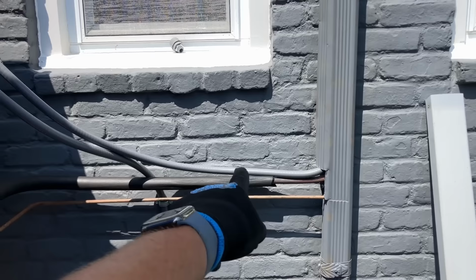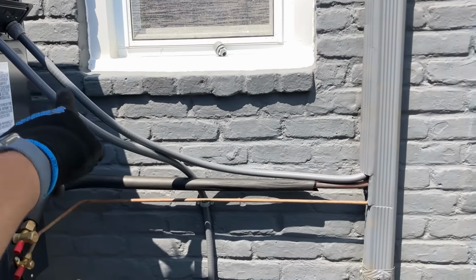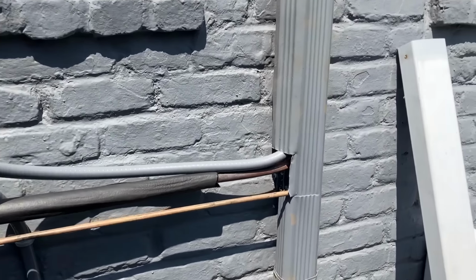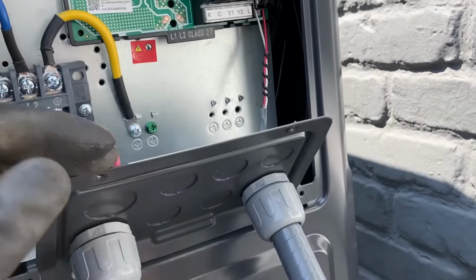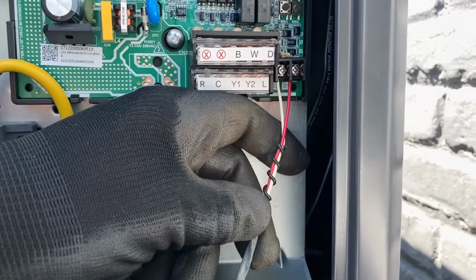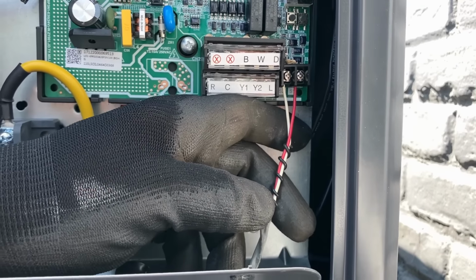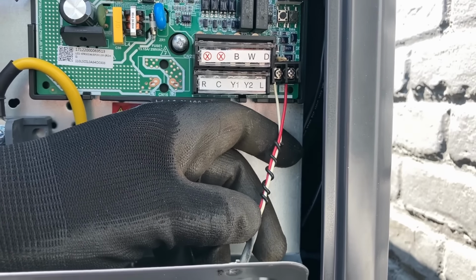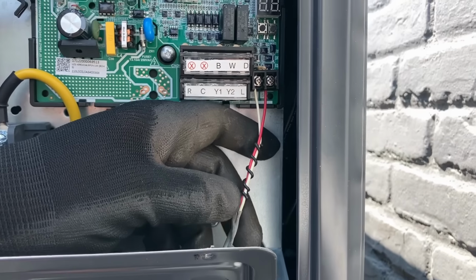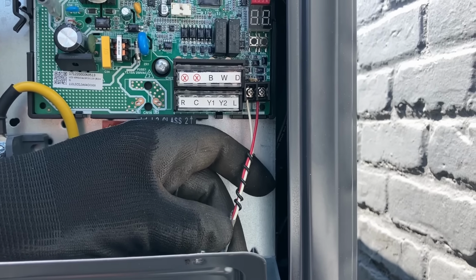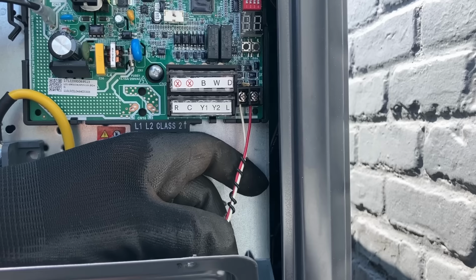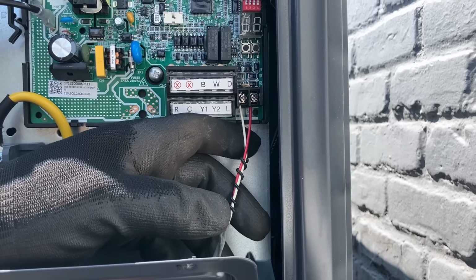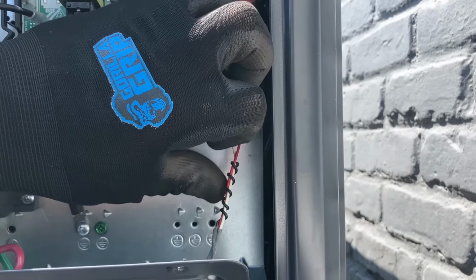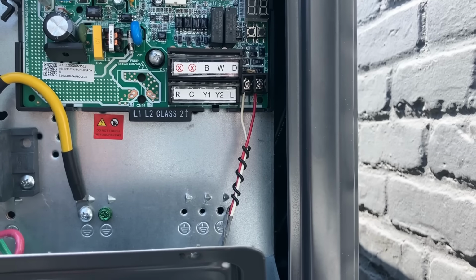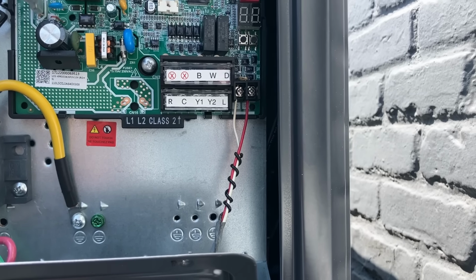But I also took some 1/2-inch Liquatite and covered up my communication wire, formerly known as the low voltage wire. It's best to use shielded wire, so if you're doing a new install, order yourself a spool of shielded 2-wire. ACiQ sells it, you can get a roll of like 1,000 feet or 5,000 feet for a very reasonable price. So especially if you're doing new construction, make sure you use shielded communication wire.